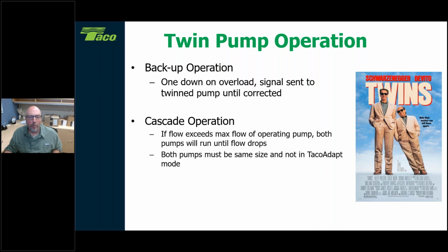Okay. Now, remembering though, when you are sizing them, obviously they both need to be the same size, and you can't use TacoAdapt in either one of them there. You're going to use either fixed speed operation or proportional pressure, or you're going to do constant discharge pressure. And what we'll also do is do an automatic alternate, all right, which means not every single time do they turn on. And when you have those 2 pumps here, twin pumps, we're always running pump 1 all the time, and maybe pump 2 never turns on until it's absolutely needed.